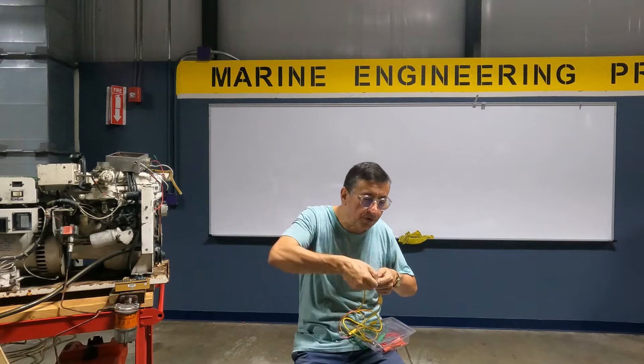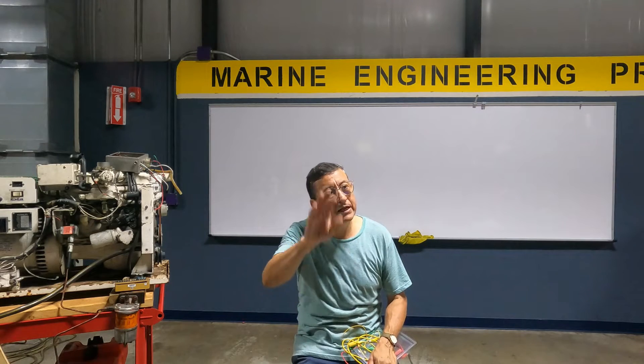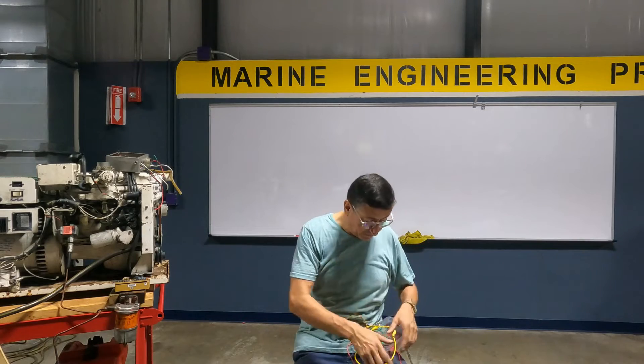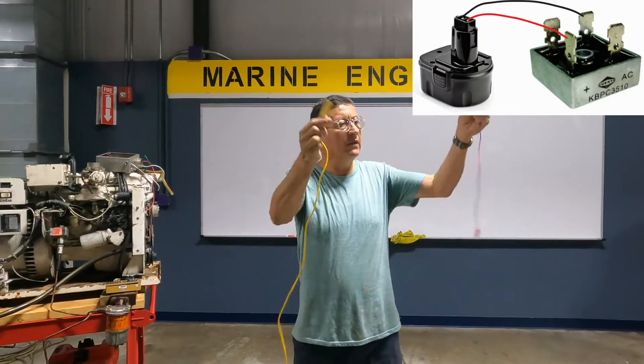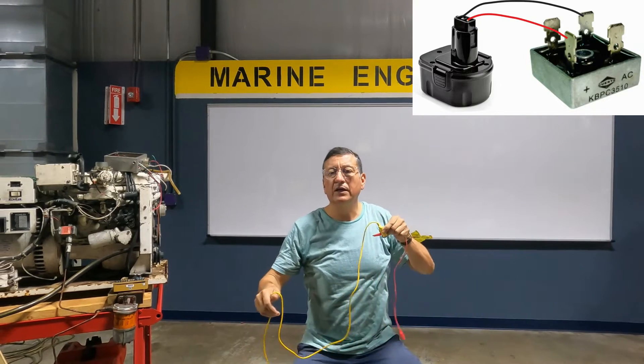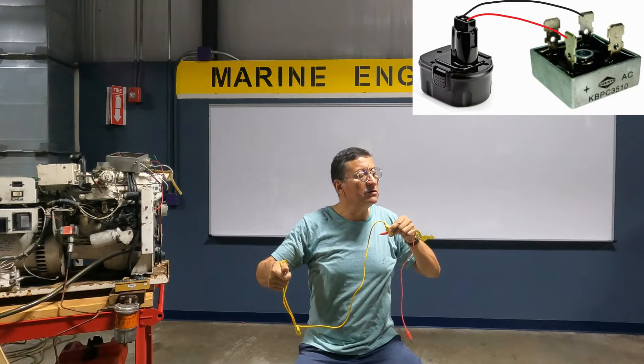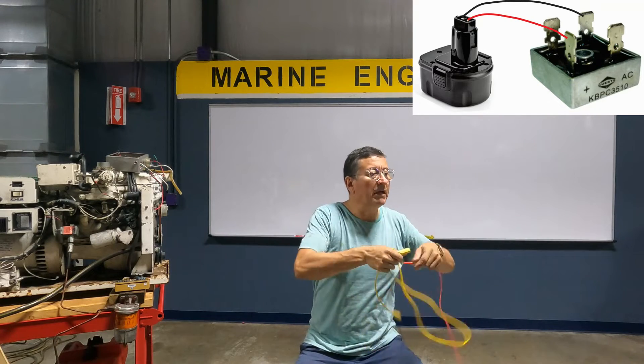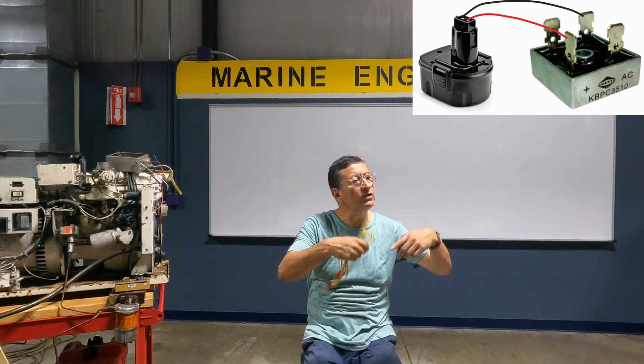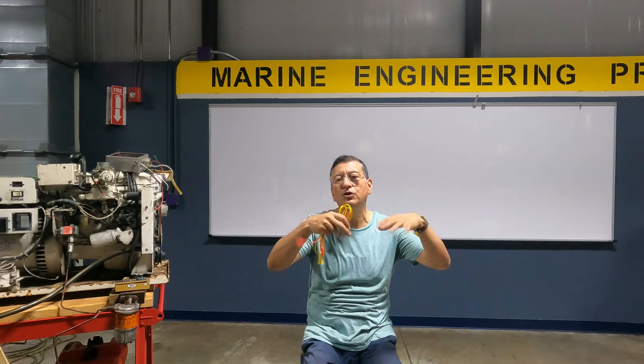After those seconds, the generator starts to produce power. Put back the original terminals and the generator continues producing power. Pay attention: connect positive and negative correctly at the DC diagonal, connect to the battery, start the generator, wait ten seconds, disconnect, and put back the original cables. Done. Now the generator is producing its own power and continues producing power.